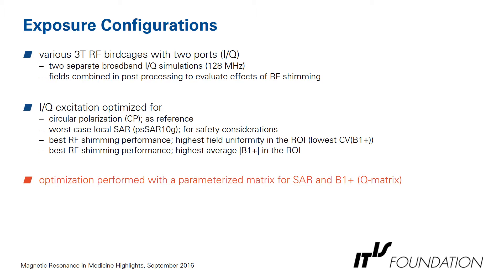The exposure configuration included two separate broadband IQ simulations at 128 MHz, with fields combined in post-processing to evaluate RF shimming effects. These two linear excitations were optimized for circular polarization (CP) as a reference, then for worst-case local SAR for safety, but also for best RF shimming performance in terms of highest B1 field uniformity and highest average B1 in the region of interest. The optimization was performed with a parameterized matrix for SAR and B1+, the so-called Q matrix.